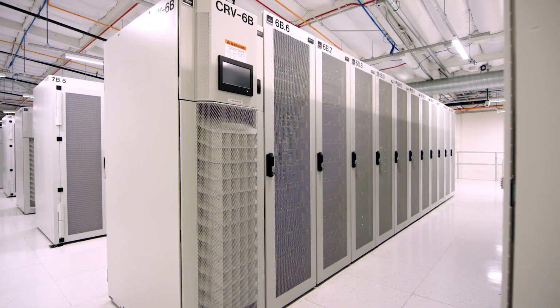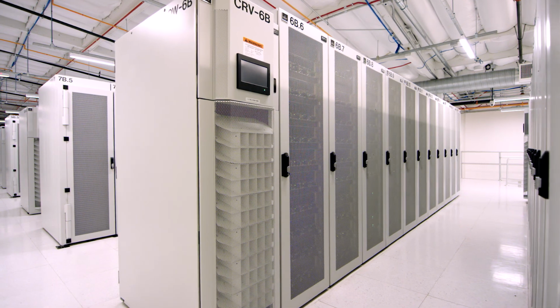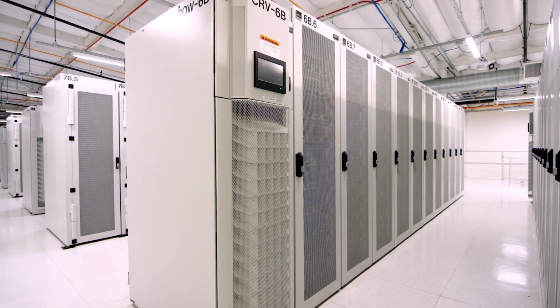So in concluding quick tip number 4, would you say that airflow management is one of the keys to HPC and AI deployments within the Colovore environment? Yes, it is. As we start to see power consumption within the cabinets go in one direction, in the direction of up, from 4 to 6 to 8 to even 35 kilowatts per rack, the direction of airflow definitely needs to be from front to back in all circumstances.